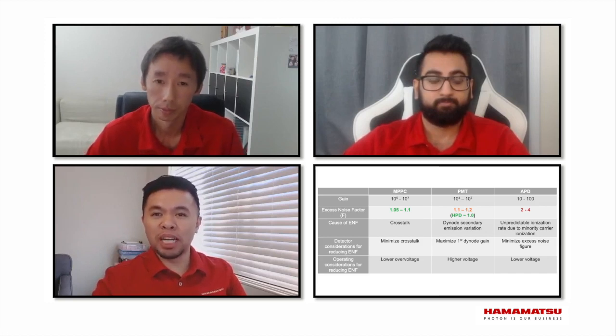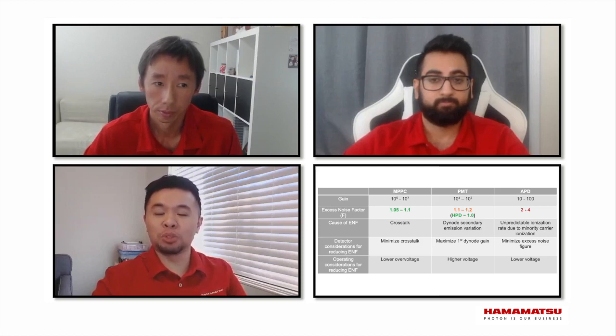That sounds like a good topic to dive into more deeply in the next podcast. For now, can you give us an idea what the typical excess noise is from best to worst for the different detectors? The best or cleanest gain would be the HPD, which has an F factor of approximately one. MPPC would be next, around 1.05 to 1.1. PMT is around 1.1 to 1.2, and APD has probably the most fluctuation with excess noise factor between two and six.